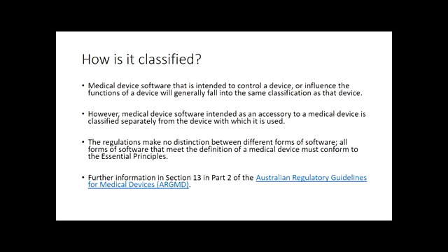All right, so basically what I said. So it'll fall in the same classification as that device. If it's an accessory to a medical device, it's classified separately. And this is interesting, the regulators make no distinction between different forms of software. So all software is the same as far as they're concerned, and if it meets the definition of a medical device, it must conform the same.